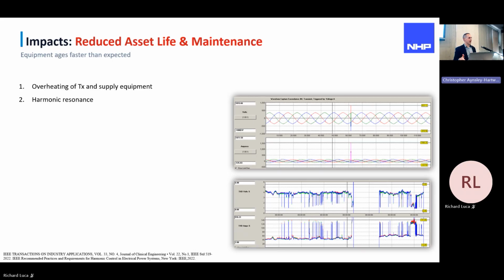Back in the electrical world, the same thing happens. When the source impedance and the load impedance are matched, and there is a particular harmonic frequency, at that resonant frequency of the system, we'll get a really large spike in current and voltage. What you see here was a case study where a site had 2 500 kilowatt drives with a power factor correction system close by. It was always in alarm mode, wasn't even operating. And the PLC system was rebooting, with network comms issues. Logging this revealed that there is a resonant condition here. We've got just over 800 volt spikes on a 415 volt system, and current spikes just over 1500 amps. This was happening randomly, at 2 a.m., 3 a.m. in the morning. So without logging, you won't be able to detect this, you'd just be replacing your failed components.